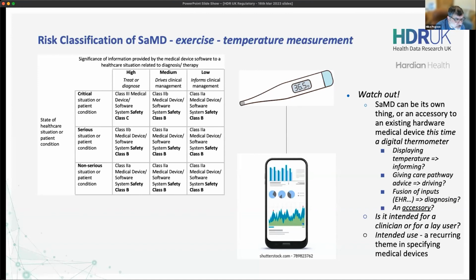Can you kindly indicate, from Shyama, which category an AI-driven remote symptom checker application that gathers symptoms from patients remotely for a GP receptionist for appointment booking purposes might fall into? That is a super gray area. Well, it's not that gray because I think we have an answer, because there have been devices done for that. Think about what I said earlier about a lay user, what's already on the screen. The receptionist is a lay user. Are you telling the receptionist that someone needs to be prioritized because of their conditions?